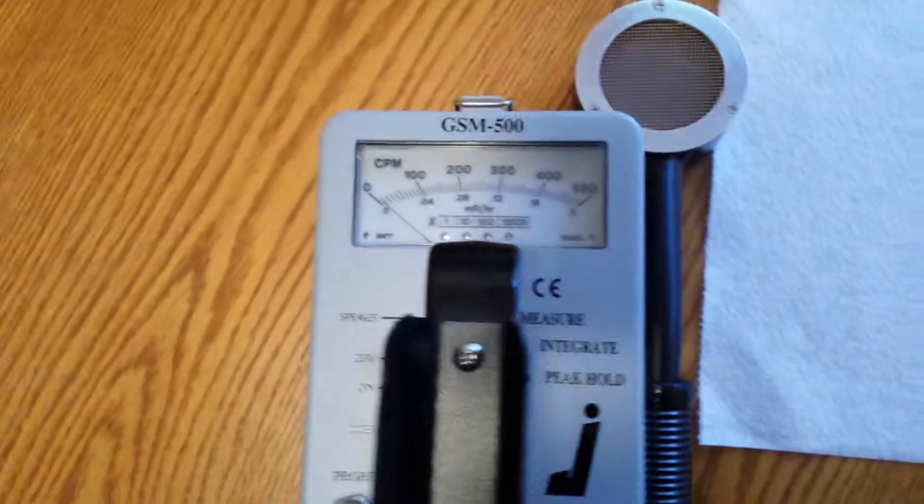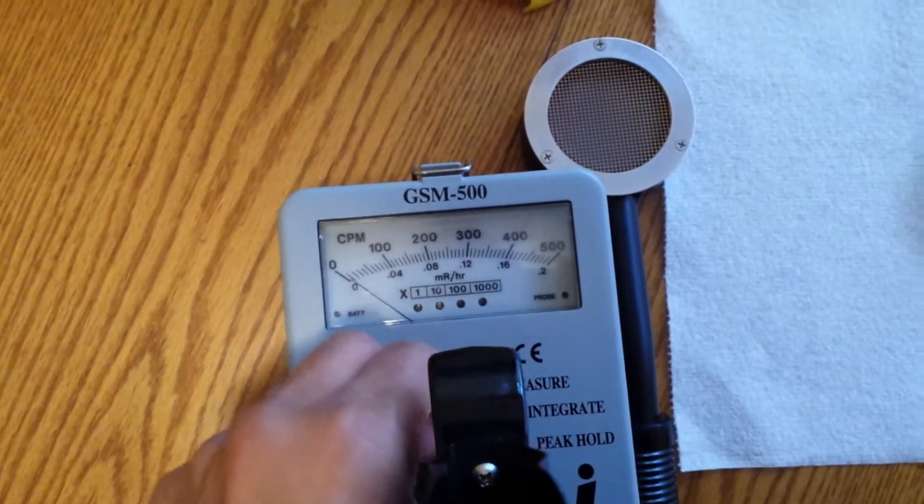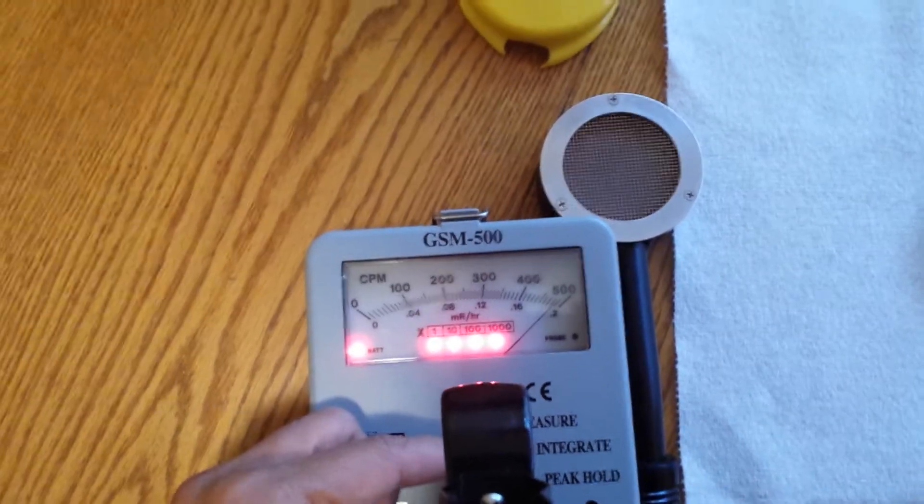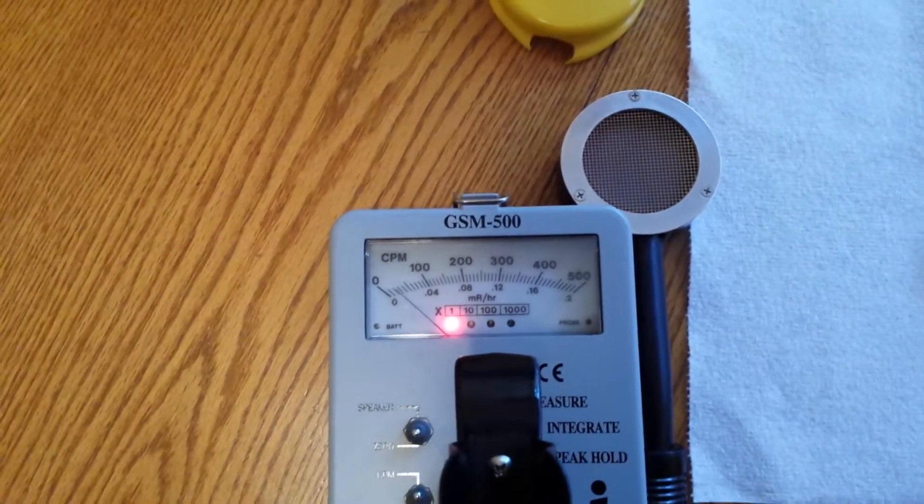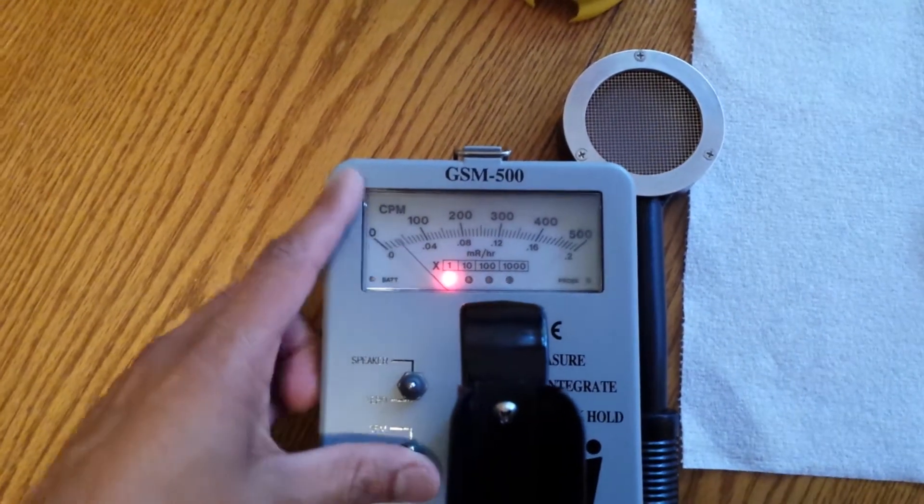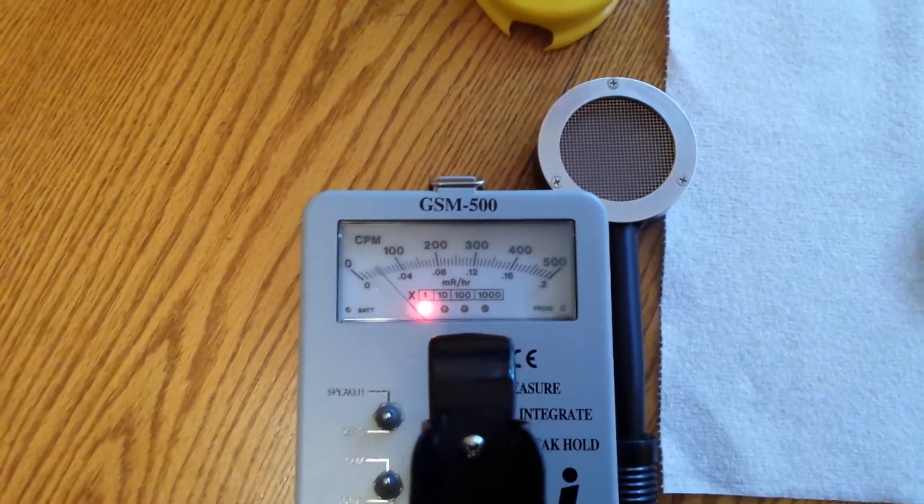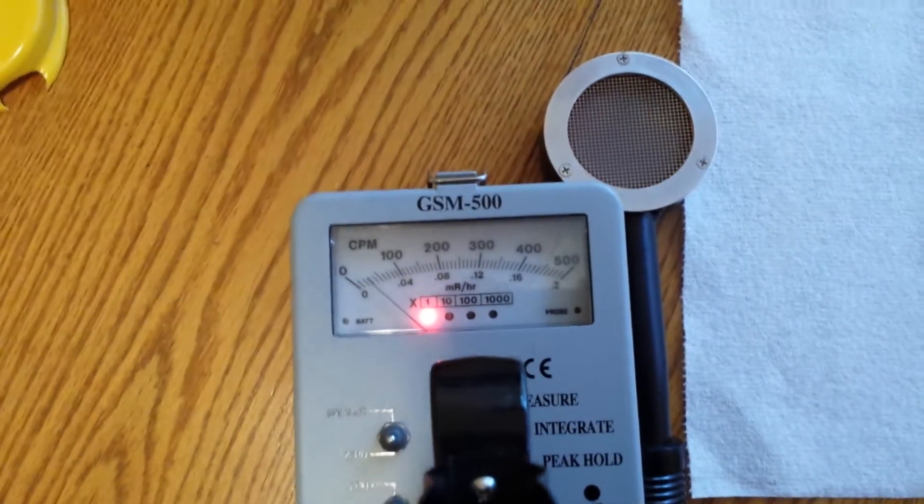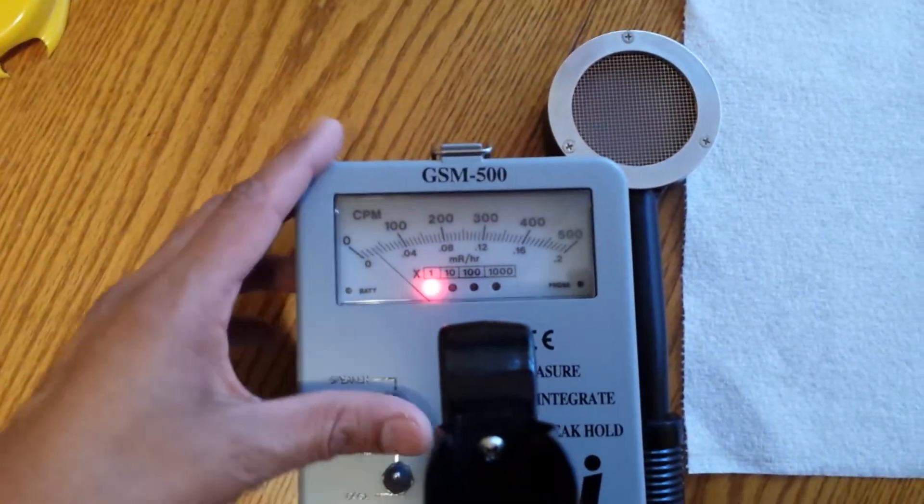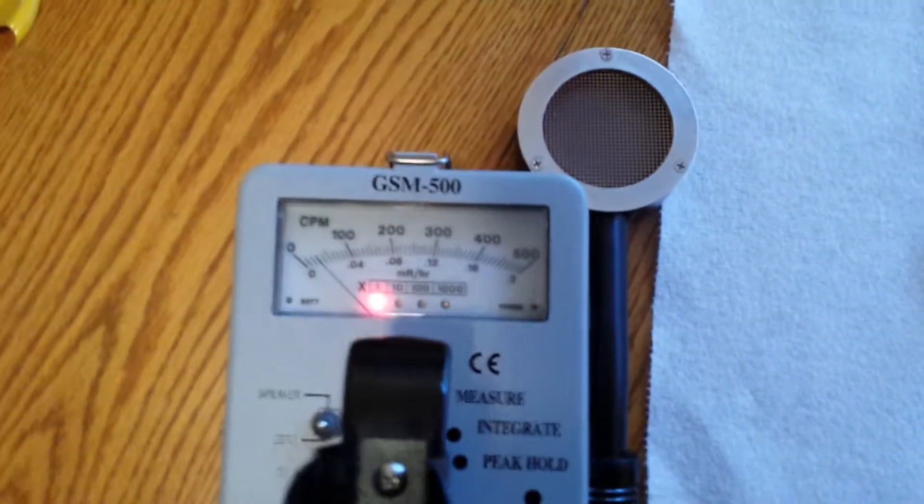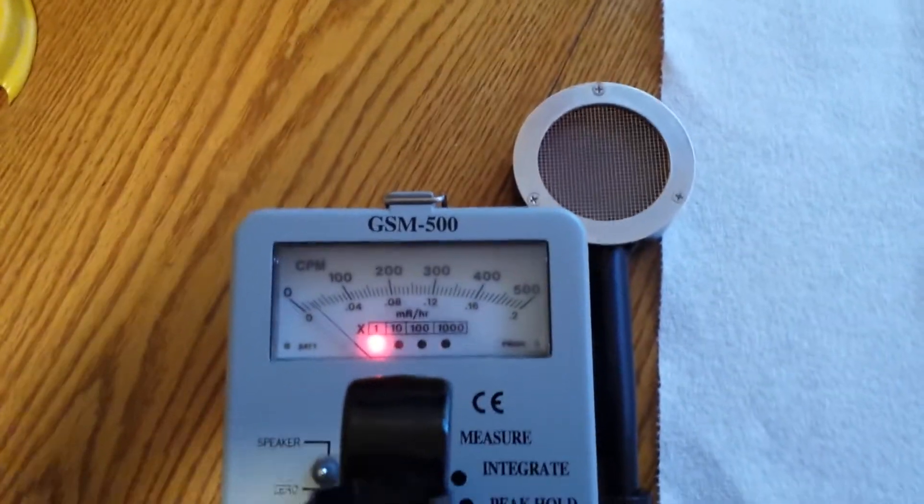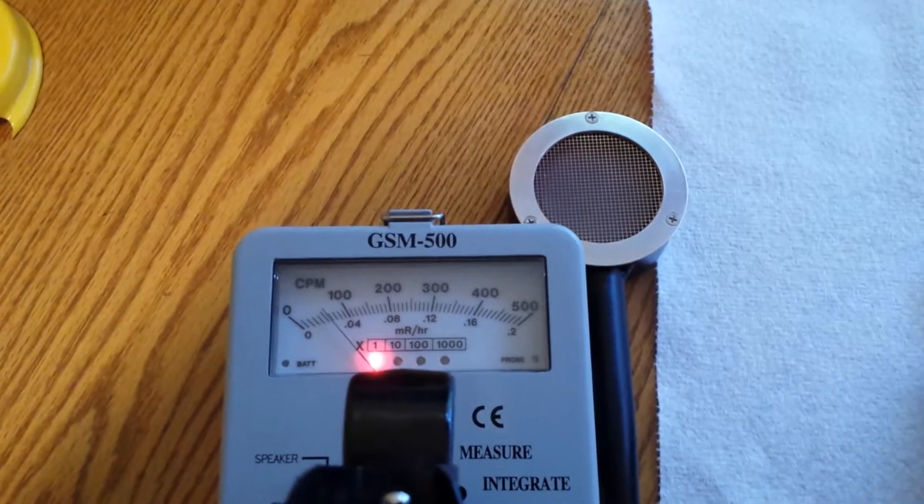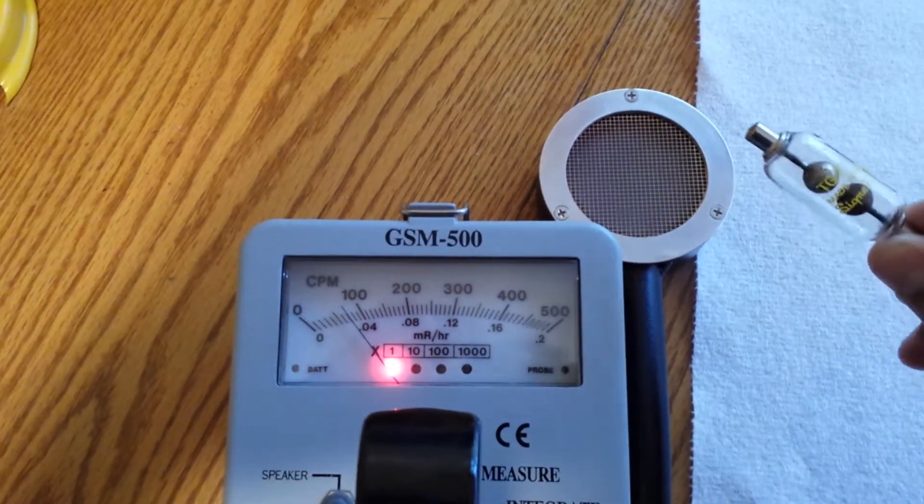So, having said that, let's start the measurements. And I'm going to go to counts per minute first and turn on the speaker. Oh, there's the speaker. That's the background level. And let me put on the test source. See what it reads with the test source.